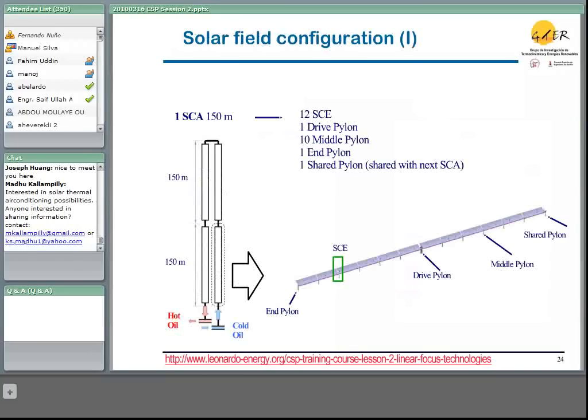The collector is the main element of a solar thermal power plant with this technology, with parabolic troughs. The collectors have to be connected between them. A collector is normally made of a set of modules or solar collecting elements, for example, in most of the collectors I mentioned before, in the Eurotrough, LS3 or Sener Trough, is 14 meters in length. In one collector you have a set, for example in this case 12 collecting elements connected rigidly between them.